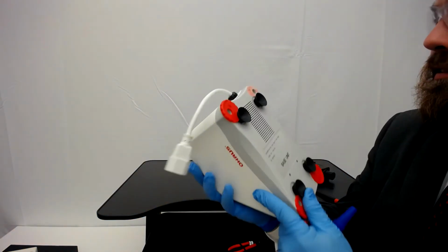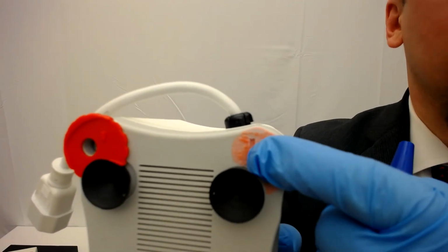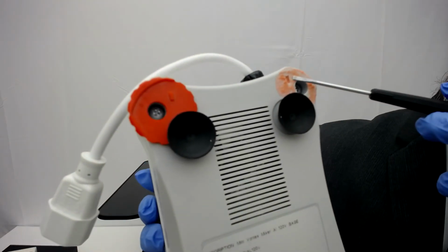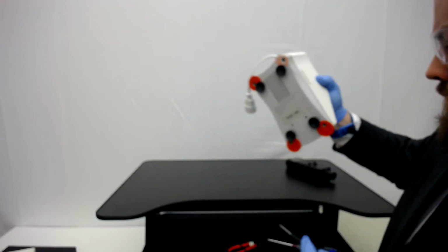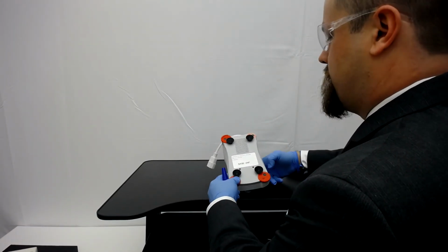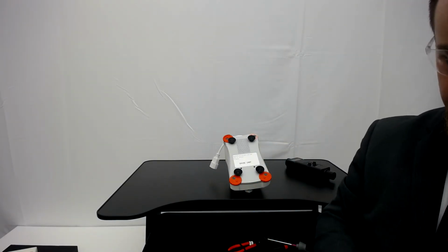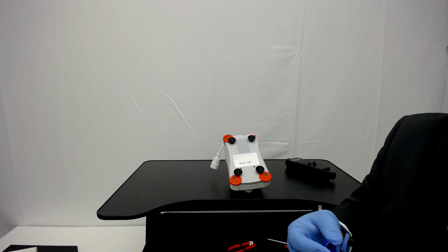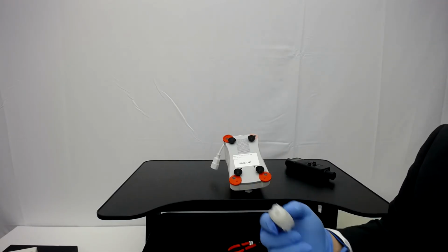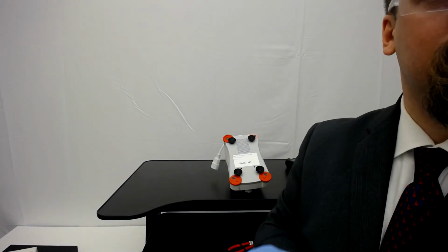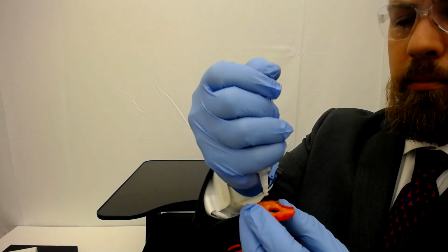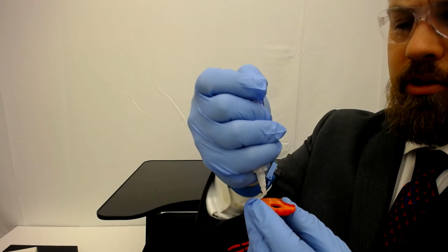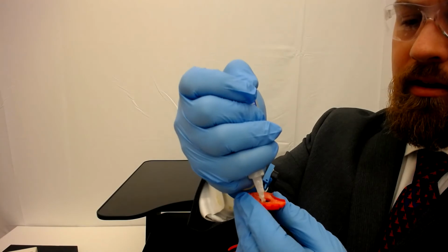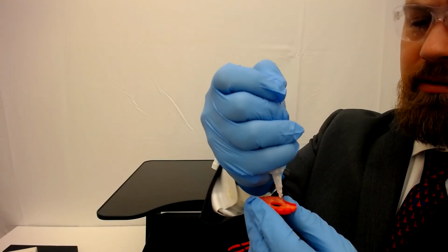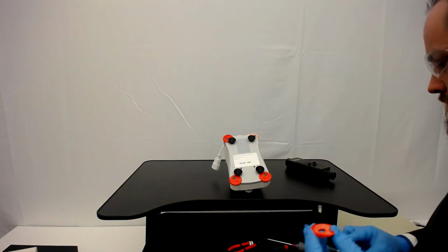Little tab right here on the bottom of this that goes into a slot here. Right there on the bottom of the unit. If that tab is broken off, again, it's not going to affect anything. That's just for positioning. Make sure that you position it correctly for aesthetic reasons, and it'll be fine. There are Loctite applicators that are shown. The important thing is that you don't put so much on that it's going to squeeze out. So we're just putting little dots of the Loctite all the way around. And it's about 11 dots of Loctite.